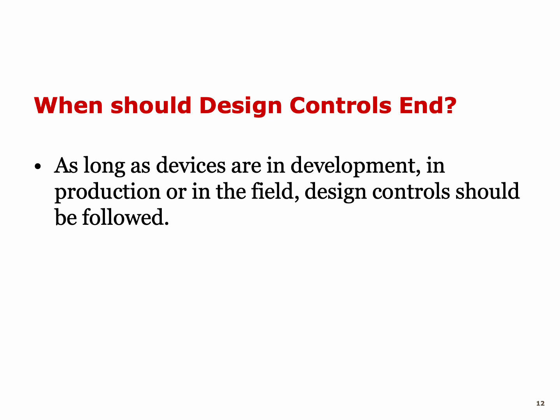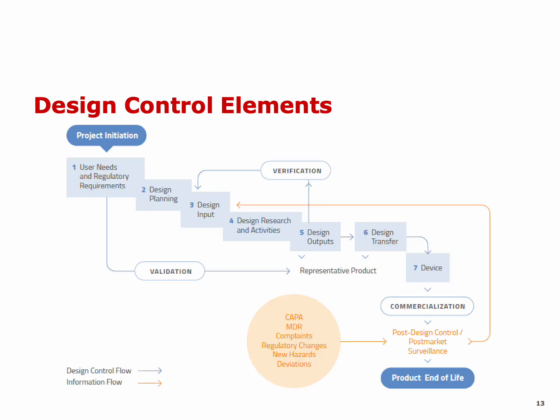Now, when should design controls end? As I already mentioned, they never end. So as long as devices are in development, in production, or in the market or the field, design controls should be followed. Now, here we are looking into the design control elements.